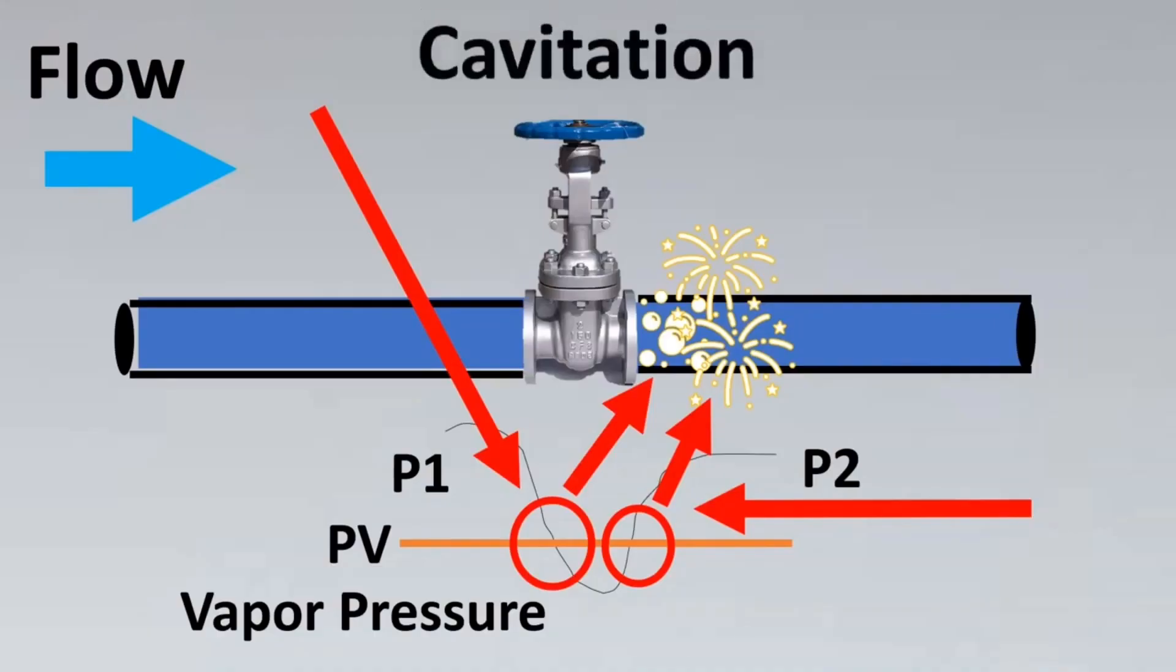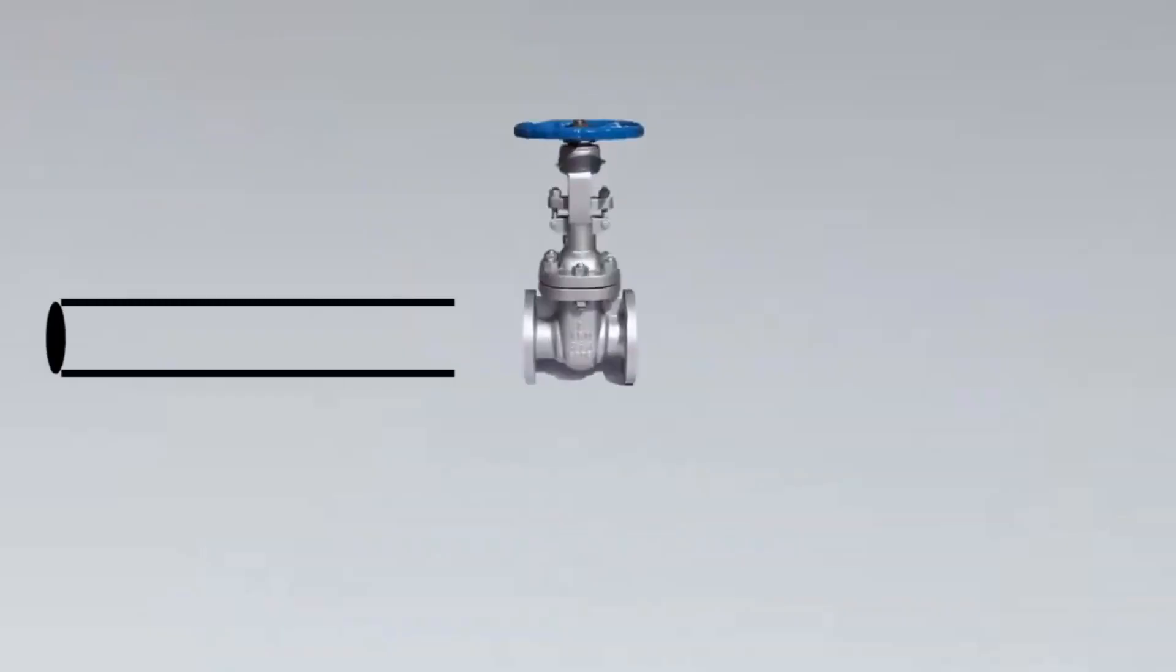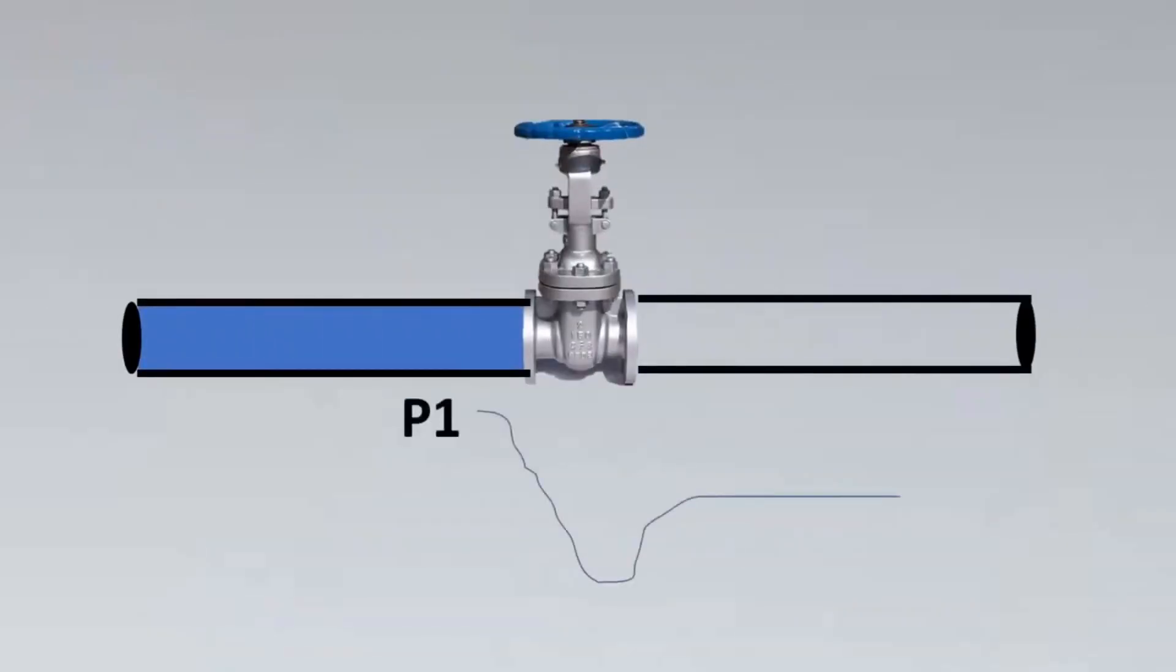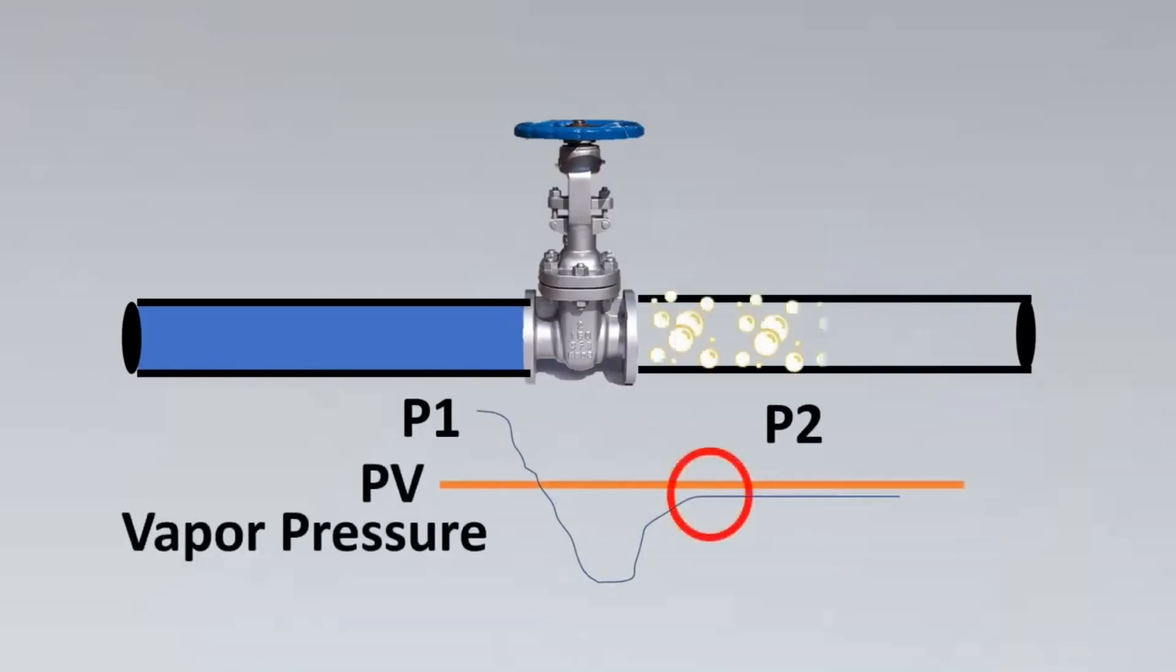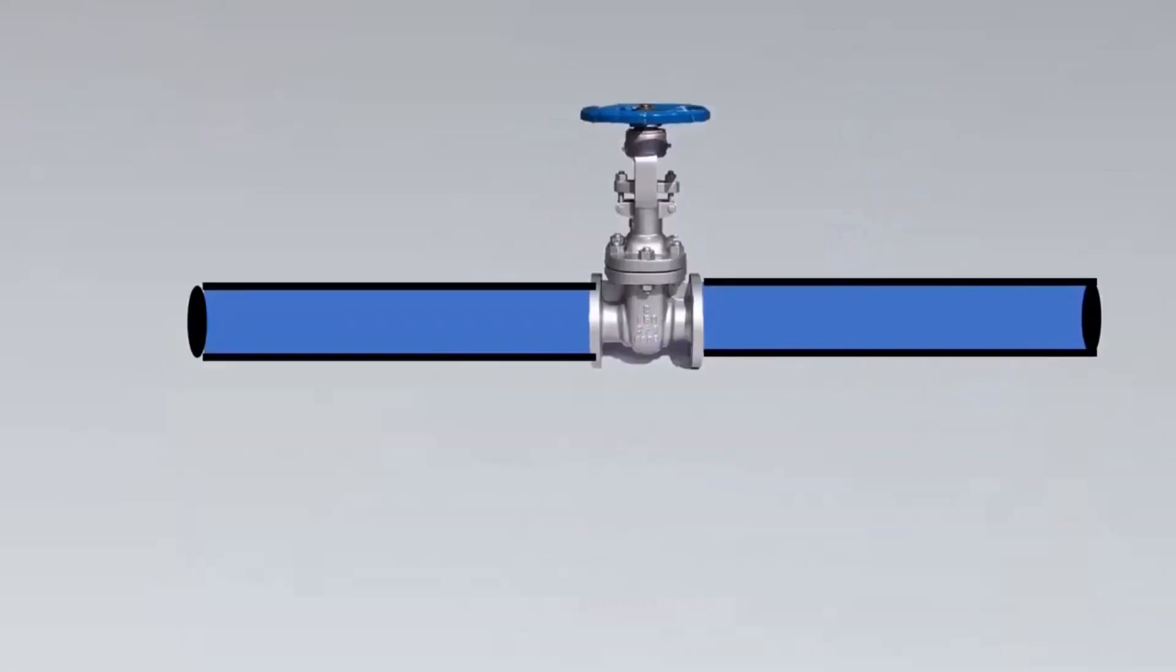The next case is when there is flow to the valve, but the pressure downstream does not recover. This happens when the pressure downstream is still below the vapor pressure curve. This makes the liquid still stay in the vapor pressure phase in the downstream, and this phenomenon is called flashing.